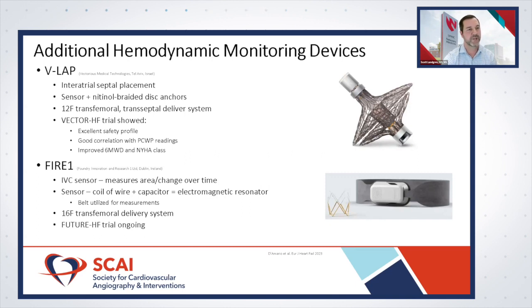The VECTOR-HF trial examined the V-LAP device and showed an excellent safety profile with no significant short- or long-term complications. It demonstrated good correlation with pulmonary capillary wedge pressure readings obtained months later via right heart catheterization, improvement in six-minute walk distance, and a statistically significant reduction in NYHA class.